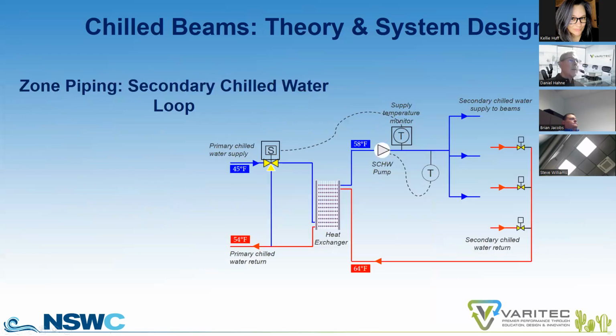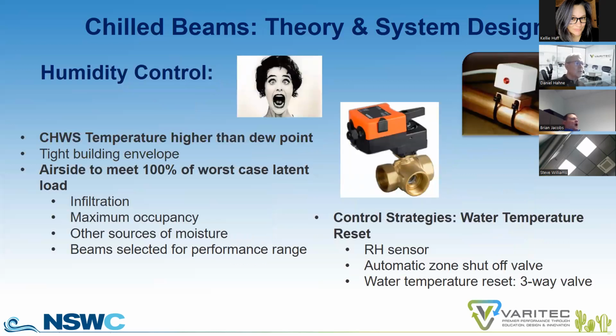Sorry about that. So what about the chill water loop to the building? Conventional designs, we normally see a primary secondary loop. The primary loop will provide 45 degree chill water to a 100% outside air unit. So you can actually provide the latent cooling you need to maintain building humidity control. And then the chiller serves a heat exchanger that will actually allow for 58, 57 degree chill water to be supplied to the chill beam loop. So that's how you decouple that. So you don't want 44 degree chill water in a space with a dew point temperature of 55. Otherwise, you will have condensation forming on the pipes and a lot of building challenges and issues.